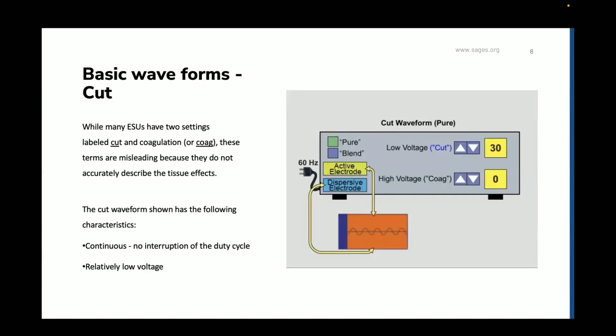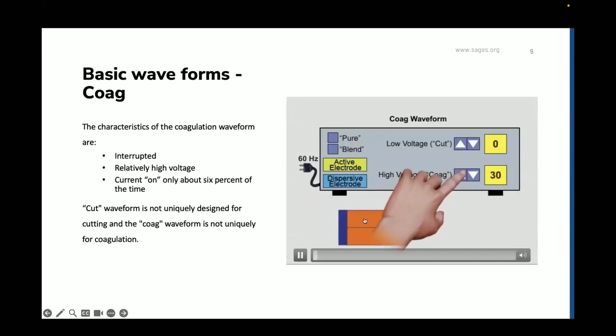and not interrupted. Compare that to coag mode, where the current that is delivered is interrupted. It's actually on almost only 6% of the time. The rest of the 94% of the time, there is no current being delivered. So it allows some cooling period between each pulse of current that is given. To achieve the same power, the voltage is significantly higher when compared to the cut form. I'll talk about how those two different waveforms achieve different tissue effects and thermal spread.